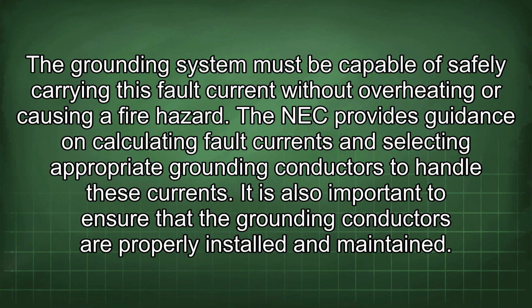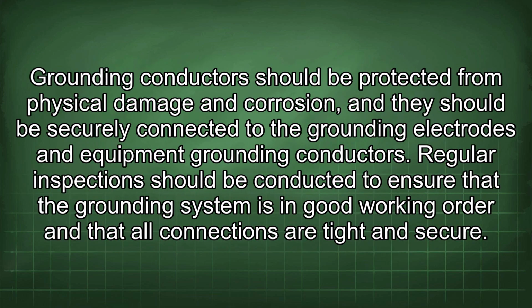It is also important to ensure that the grounding conductors are properly installed and maintained. Grounding conductors should be protected from physical damage and corrosion, and they should be securely connected to the grounding electrodes and equipment grounding conductors. Regular inspections should be conducted to ensure that the grounding system is in good working order and that all connections are tight and secure.